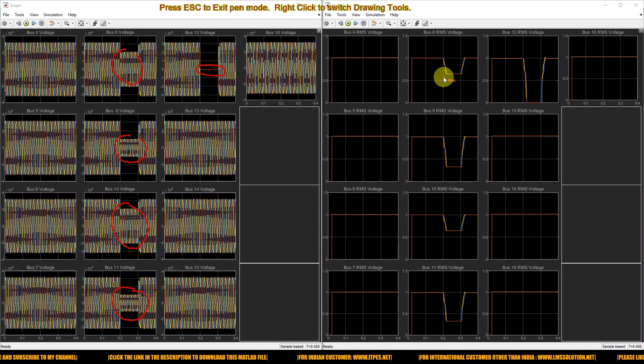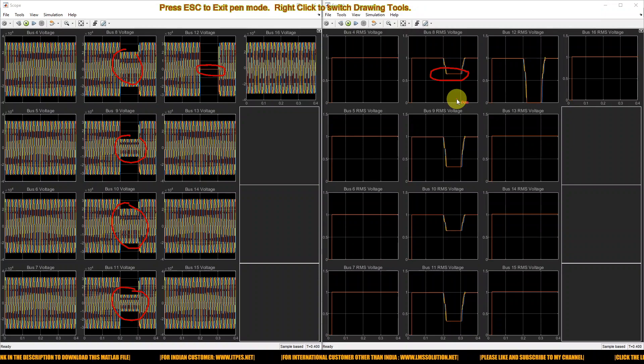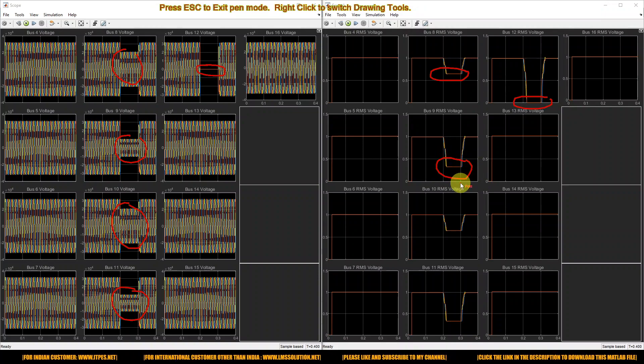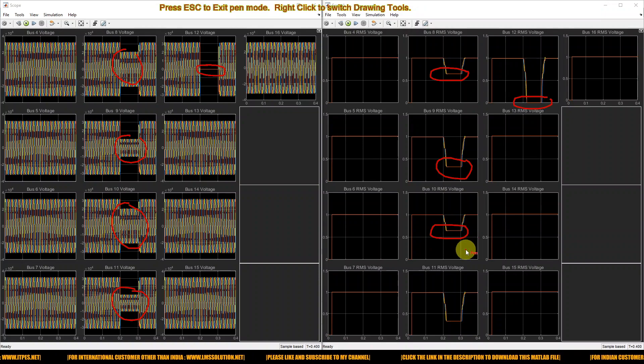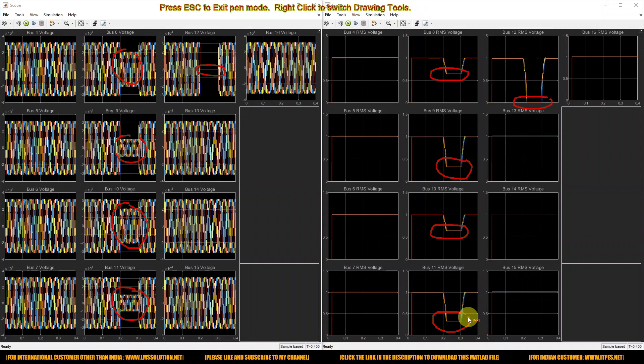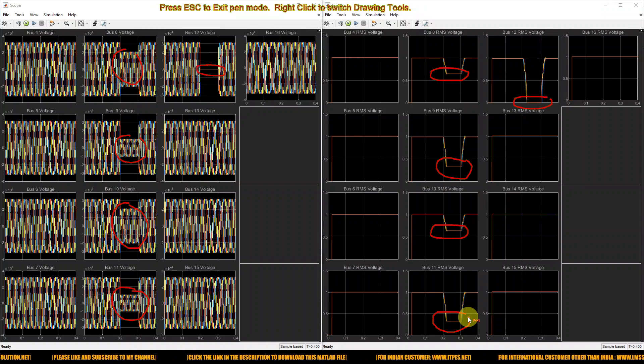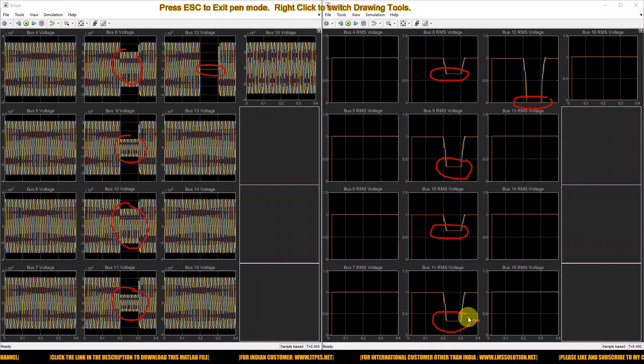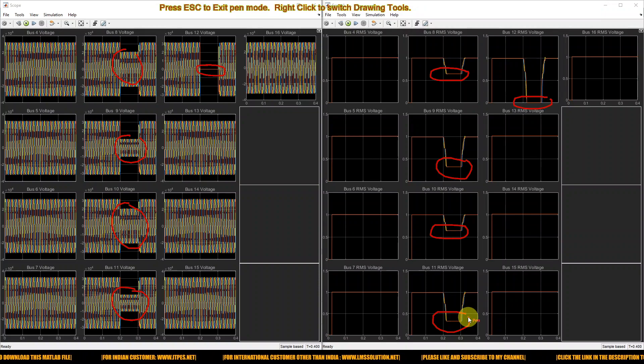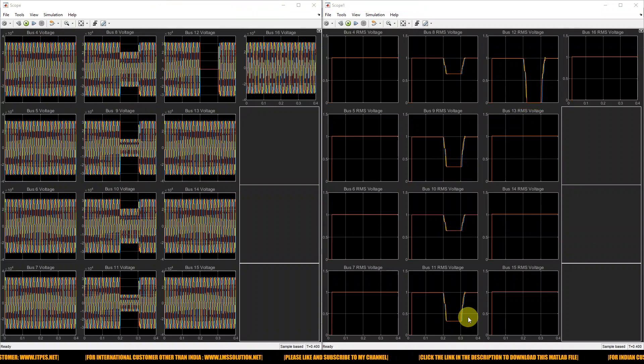Looking at the RMS voltage deviation: bus 8 drops around 40%, bus 12 drops around 100%, bus 9 drops around 70%, bus 10 around 60%, and bus 11 around 70%. The fault at bus 12 affects all remaining buses. We need to mitigate this voltage sag to protect the system and maintain bus voltages at 1 per unit.